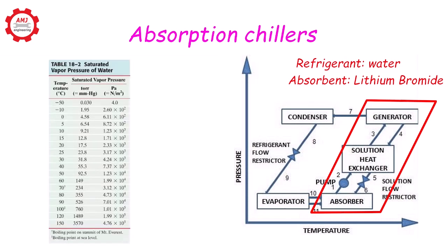Note that the absorption chiller must operate at very low pressures, about one over one hundredth of normal atmospheric pressure, for the water to vaporize at a cold enough temperature, for example at 40 degrees Fahrenheit, to produce 44 degrees Fahrenheit chilled water.